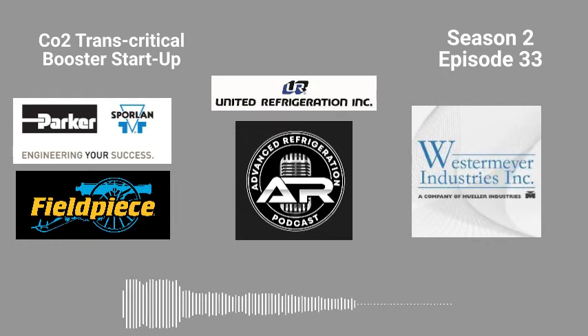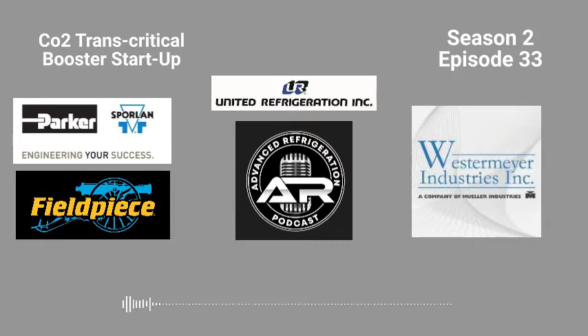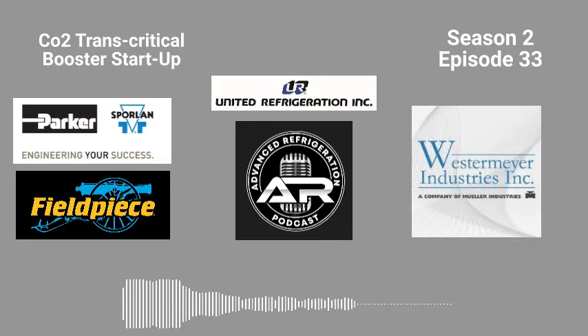Yeah, and then once you get all that done, what you're going to want to do is make sure you get your 24-hour pressure test and then blow it down. Now, because every one of these racks is so filthy dirty, I try to blow it down out the liquid core. So I'll valve off the liquid shell dryer if it has one, or the suction shell dryer if it has that, and I will blow all the nitrogen out of that. I'll pull the plate off and blow it down that way.